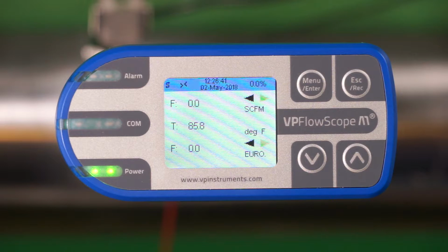If the status icon is blinking black, the transmitter is trying to find a network. If the icon is continuously black, the transmitter has connected to a network. And if the icon is continuously red, the transmitter failed to connect to a network. One tip: if your status icon is red, please go to the Wi-Fi status menu, which we will show you later on. This will give you a first indication of what error occurred.